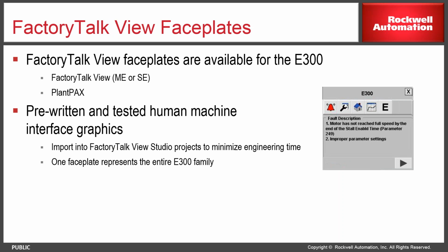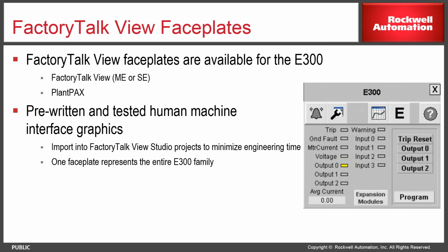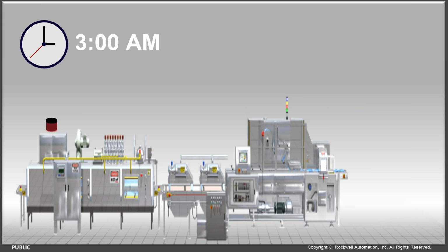Up to five trip and warning events are logged into the trip and warning histories, which are stored in non-volatile memory. Maintenance personnel can use the trip and warning history information to see if any trends exist that could indicate any more system-related issues. So these are the various warnings.